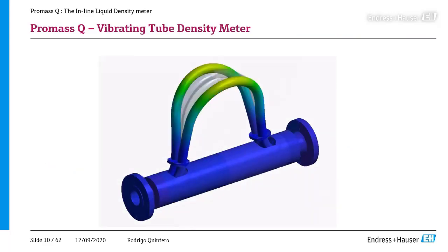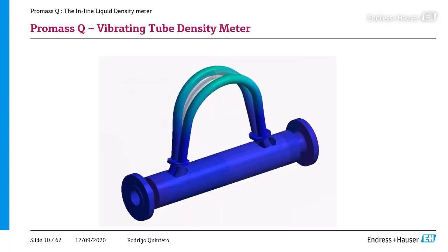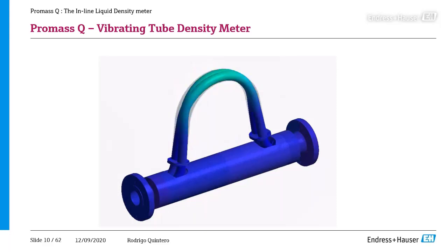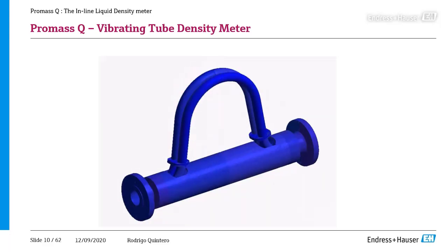So going ahead, how does the Coriolis meter measure density? If we see the image right here, a Coriolis meter contains two bent tubes, right, through which the flow passes. An electromagnetic driver system causes the tubes to vibrate toward and away from each other at the resonant frequency. And the frequency is determined by the tubes' stiffness and their mass, of course. For example, when no medium is flowing, the tubes will oscillate uniformly. But when there is a medium flowing, the tubes will twist proportionally to the flow rate. Then a phase shift occurs between the first and second sensor.